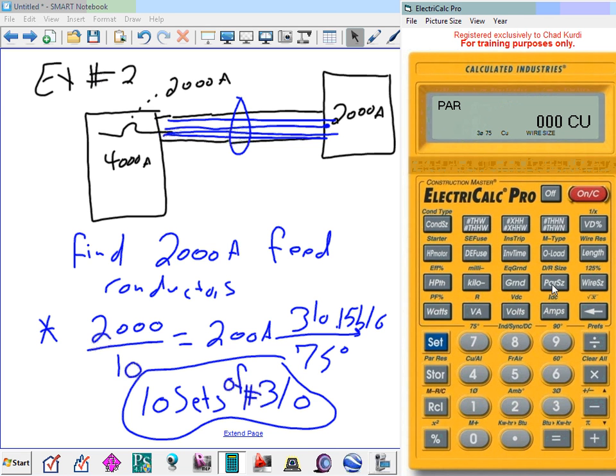Okay, now I'm going to make it more interesting. I'm going to put all these 10 runs in one conduit. Now tell me where on earth you can put these 10 runs in one conduit. Cable tray, but you don't have to do it. Let's just assume we're going to put all these conductors in one conduit, all of them. I have 10 of them. 10 times 3 is what? 30 current-carrying conductors. The neutral counts 0 because the neutral has no harmonics.